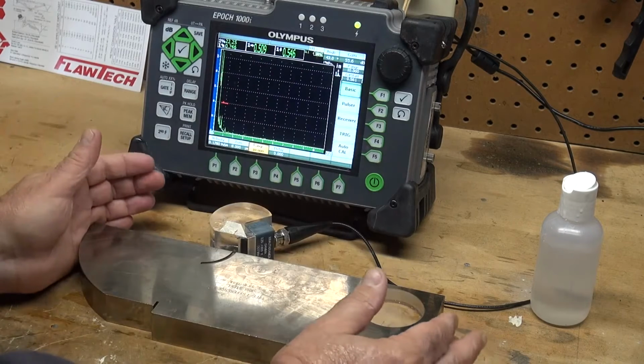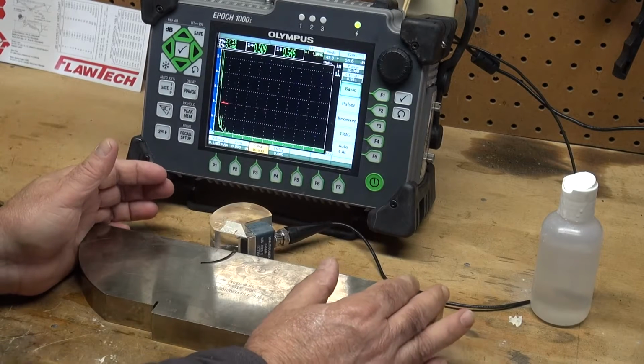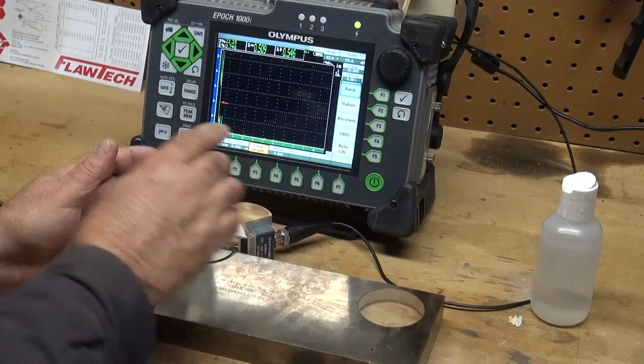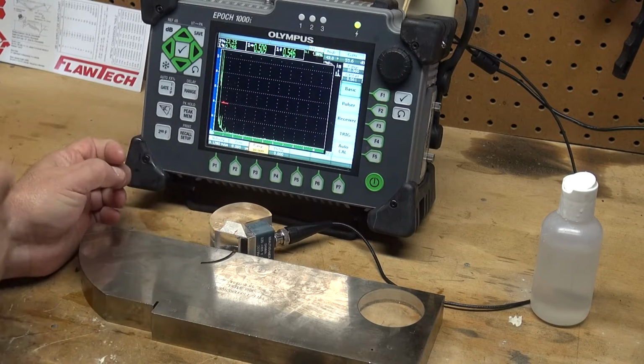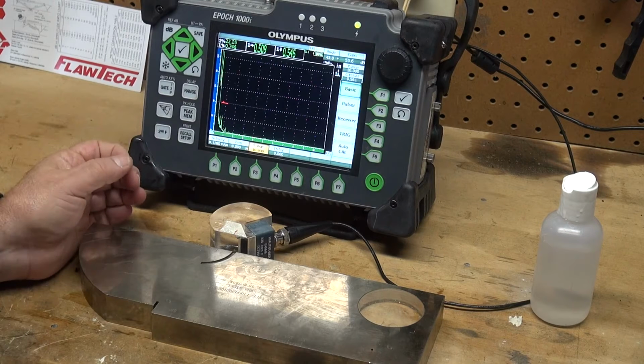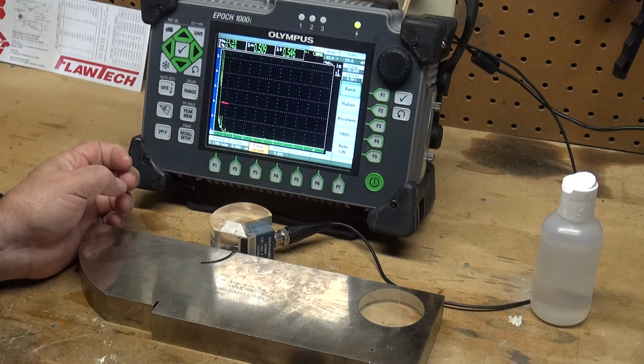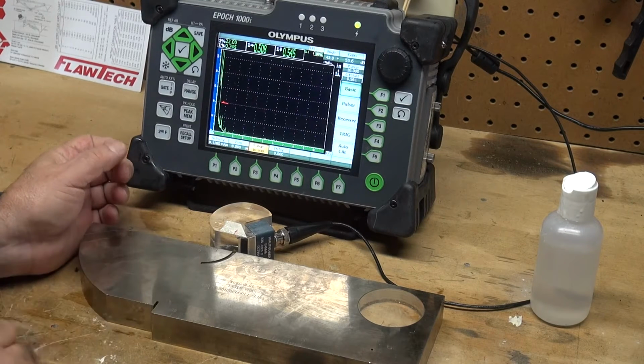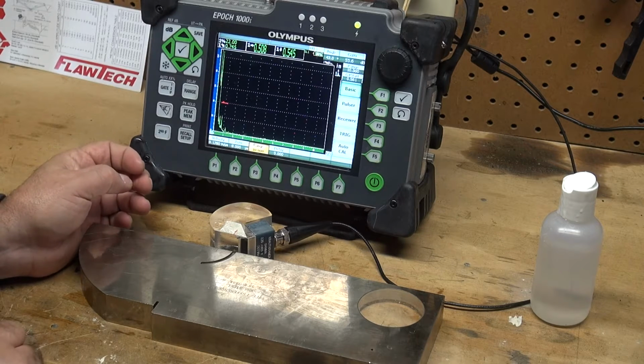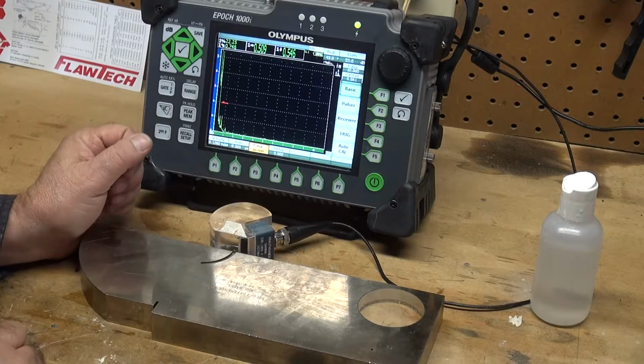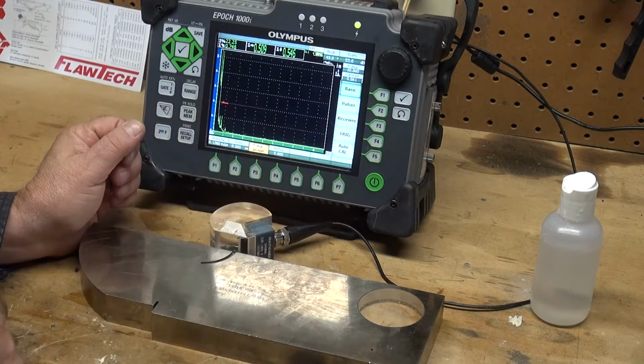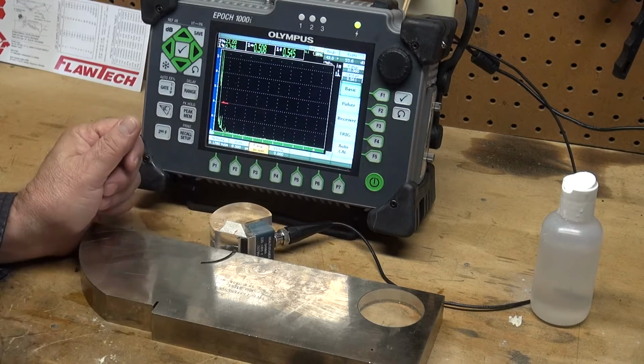Like I said, I set my range at 10 inches for the Type 1 IIW block. And the velocity, I set it at 0.128 inches per microsecond, which is your standard carbon steel, mild steel shear velocity. The zero is set at 0. I'm going to let my AutoCal take care of the zero in the wedge.